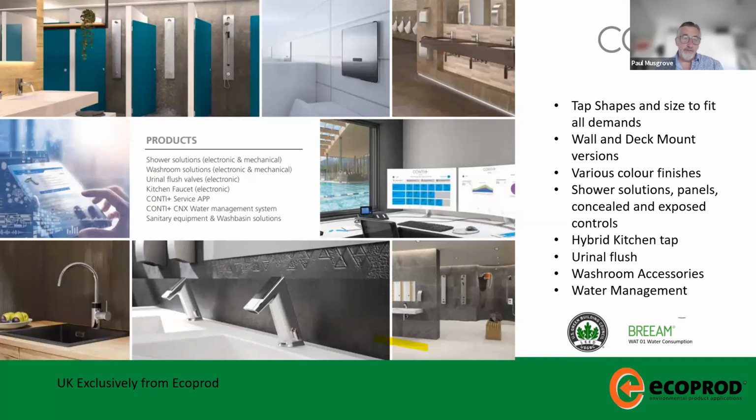The other important point for design is the water pressure. So Conti's products are tested to work from 0.3 bar and tested up to 10 bar, and it will work consistently. And that's a really important point for the M&E consultant to understand as well, because when he's designing his building infrastructure based around the selection of products you've made, he may need to, with other products, other manufacturers, put in water booster points in parts of the building which have a cost and an installation cost. So it's a cost saving by selecting this product.